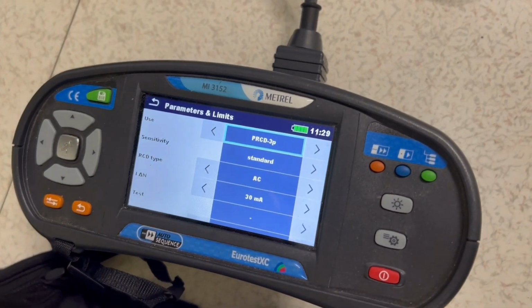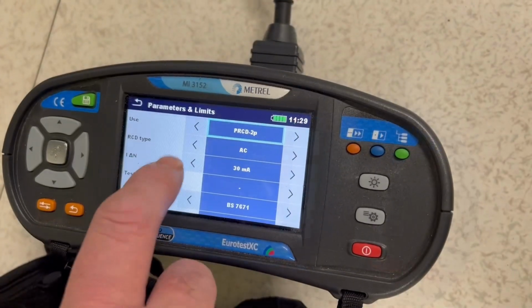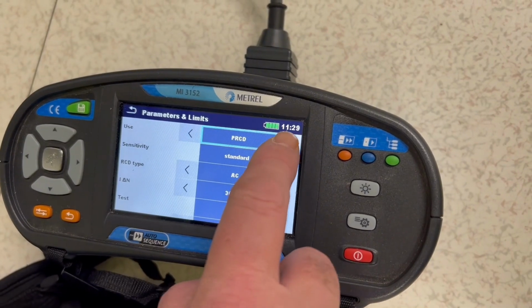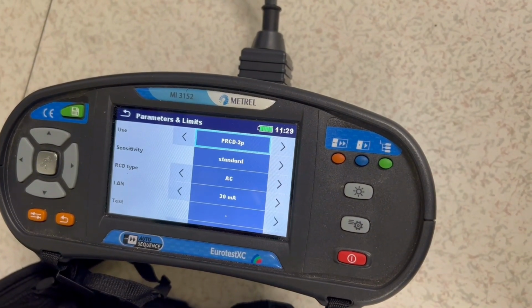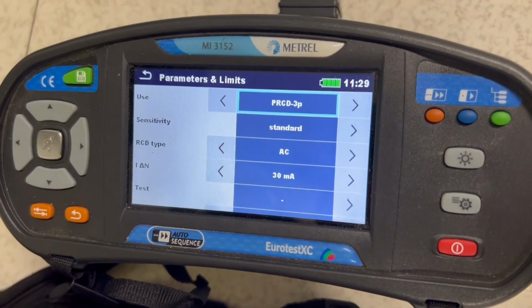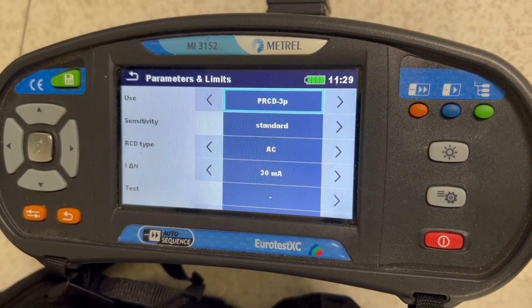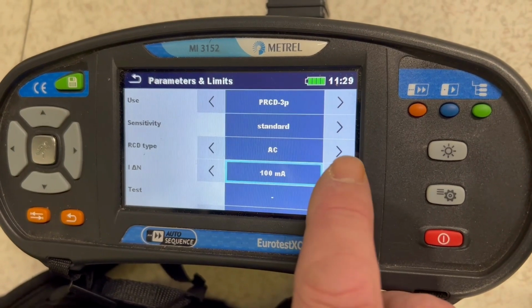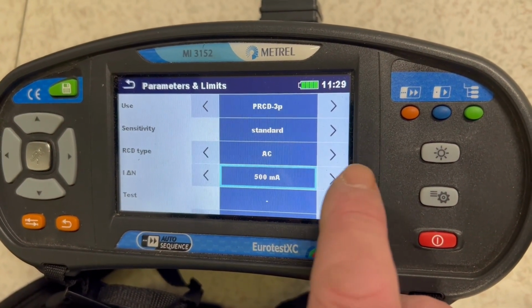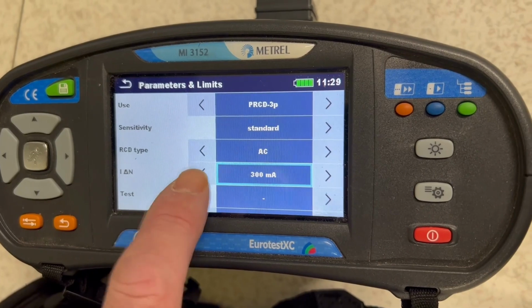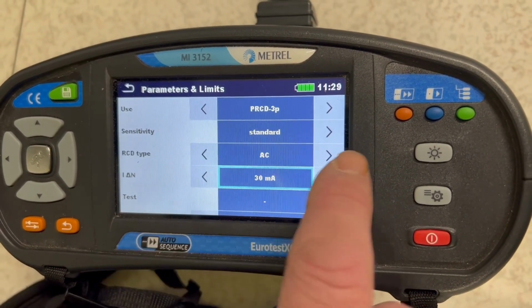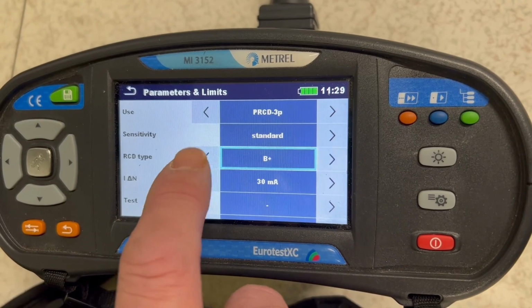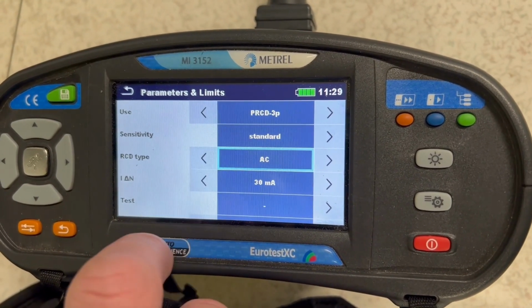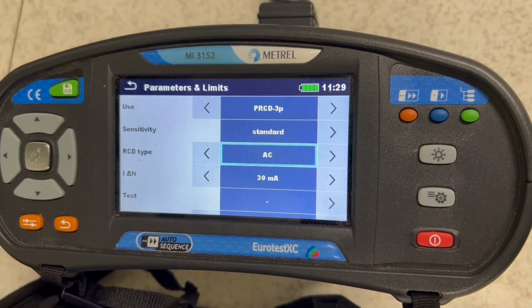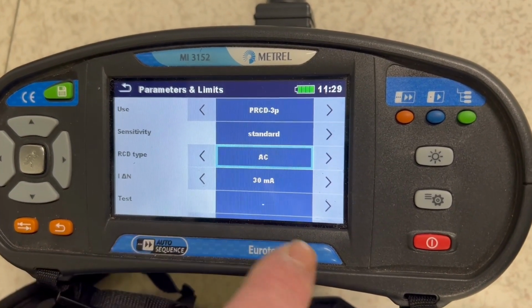Under this option we have the option to set in what kind of device it is, 3 pole, 2 pole, single pole, what the sensitivity of the unit should be, the RCD type and the tripping current value. We have options 30 milliamps, 300, 100, 500. There's multiple functions available here, and we can also select the RCD type. Below we can test to certain standards.